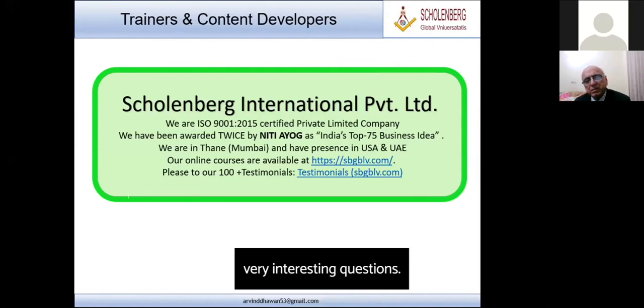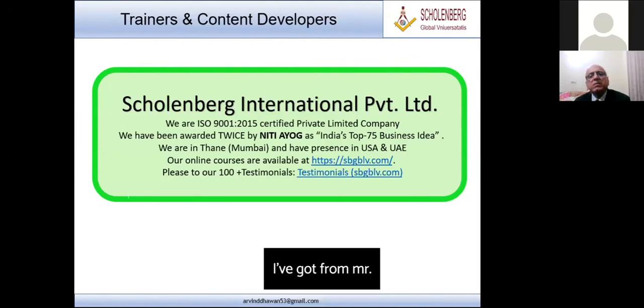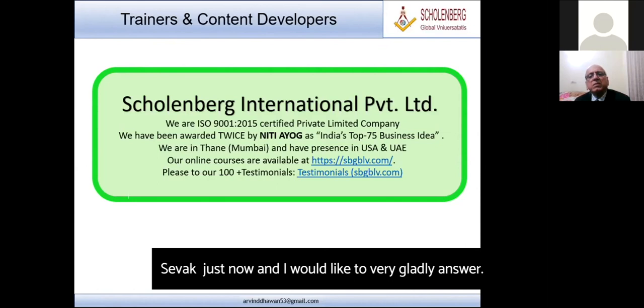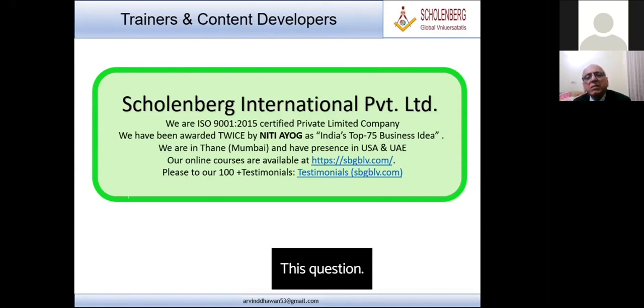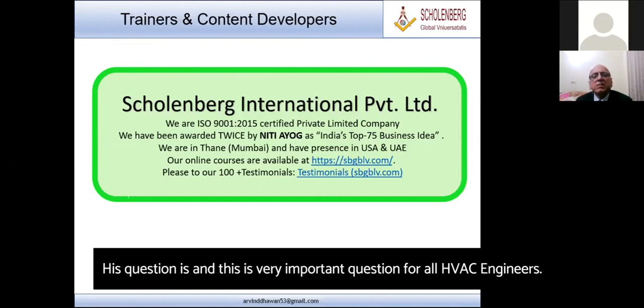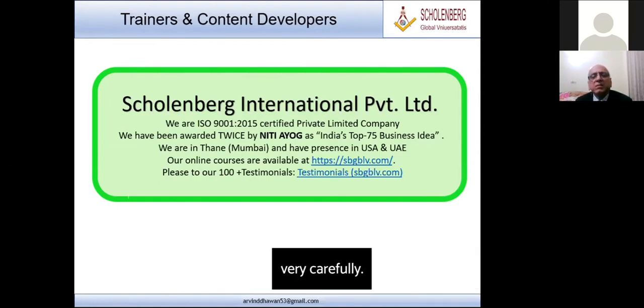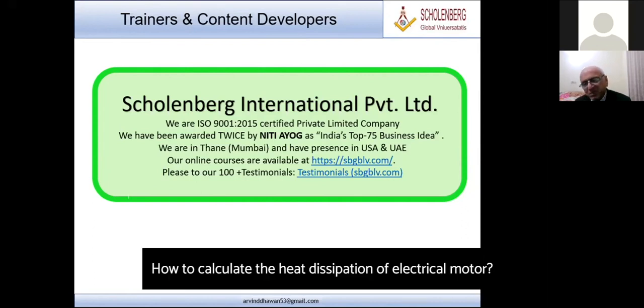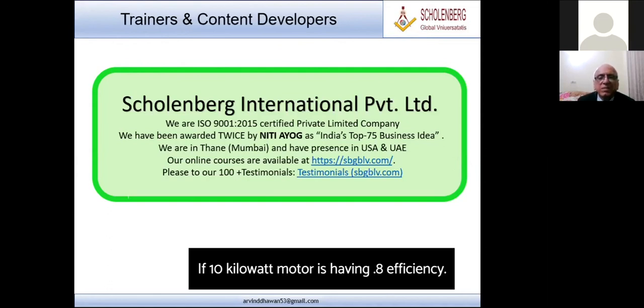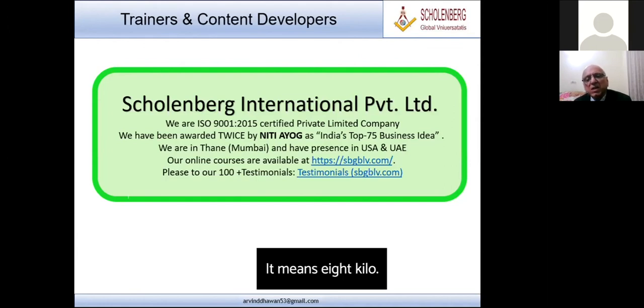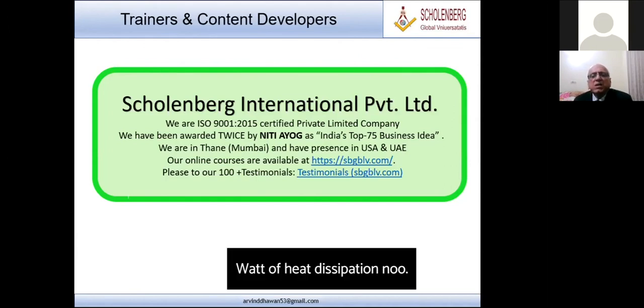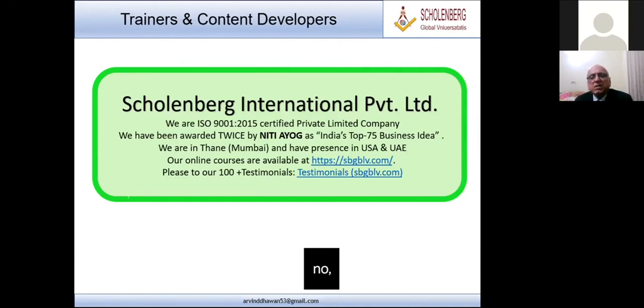So this is a very interesting question I got from Mr. Hemant Sevak just now, and I would like to very gladly answer it. This is a very important question for all HVAC engineers. Please listen to it very carefully. How to calculate the heat dissipation of an electrical motor if a 10 kilowatt motor is having 0.8 efficiency? It means 8 kilowatt of heat dissipation? No, a big no. Please understand, this is a big no.